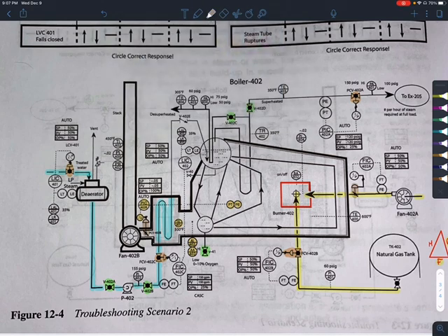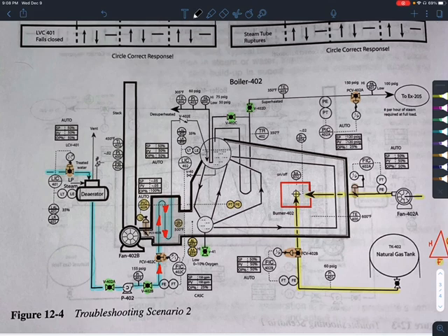So within here, it is called the economizer. The purpose of the economizer is to preheat this water going into here. And what's heating the water is actually the combusted gas in here. So that combusted gas heats the water. Let me get rid of these arrows.